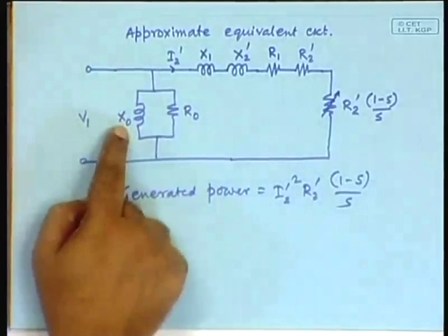Reactive power is generated by capacitances and consumed by inductances. So here is an inductance that consumes the reactive power, and so the grid has to have some capacitance in order to generate that reactive power. And so if you have a wind farm or a large number of wind turbine generators at one place, it is usual practice to place a big capacitor at that spot, so that the reactive power is generated right there, and that is what gives the reactive power into this supply.